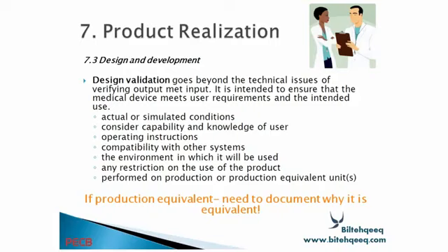Actual or simulated conditions consider capability and knowledge of user, operating instructions, compatibility with other systems, the environment in which it will be used, and restrictions on the use of the product performed on the production or production equivalent units. If production equivalent, need to document why it is equivalent. So you have to document each and everything.